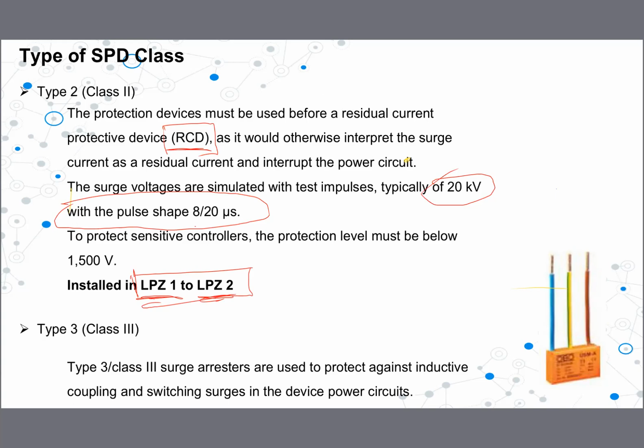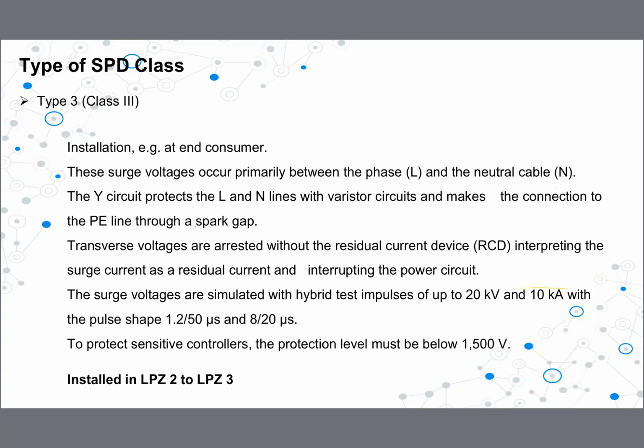Then we have type 3 SPDs. Type 3 SPDs we mostly use at the terminal end of the equipment, at the final level. So type 3 we use in zone 3, right? So we use between zone 2 and zone 3. So the pulse shape is this one, and the voltage level and current is this. And the protection level should be below 1500 volts. This also I will explain later, right, with another graph.